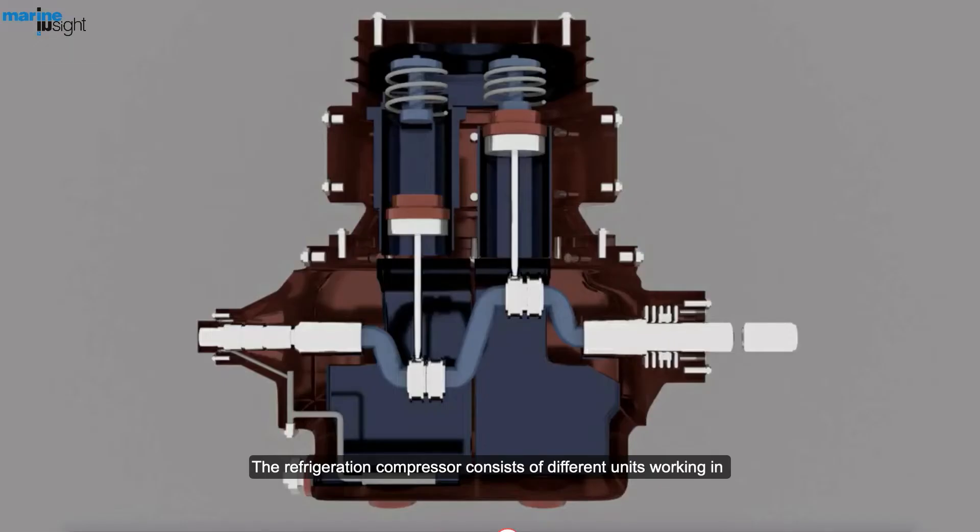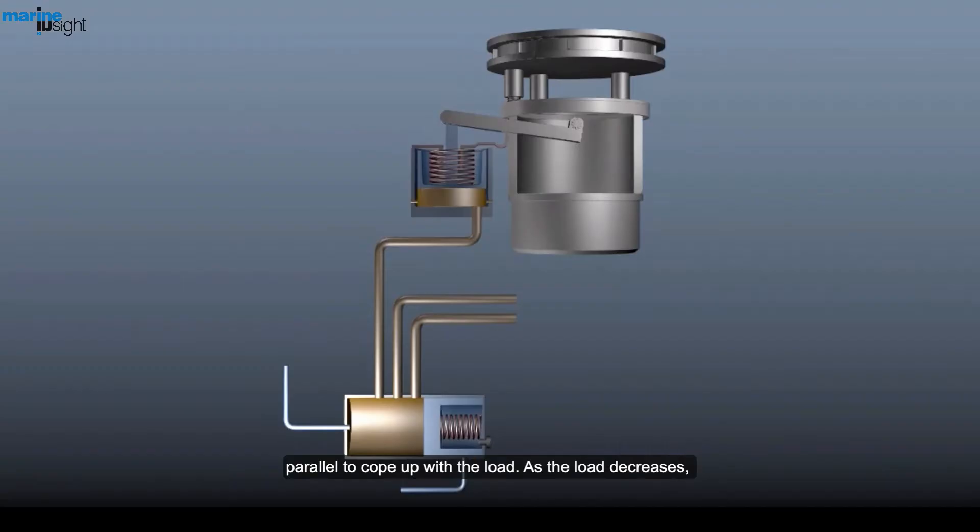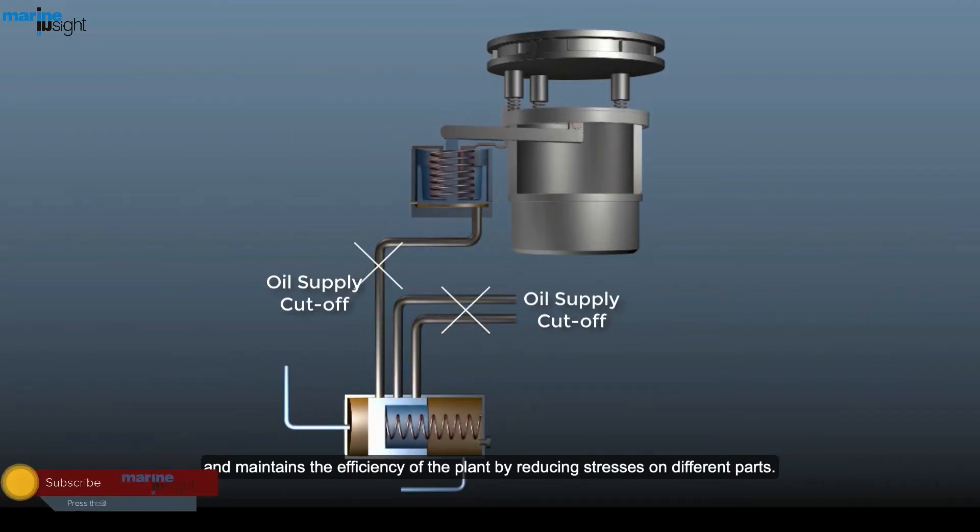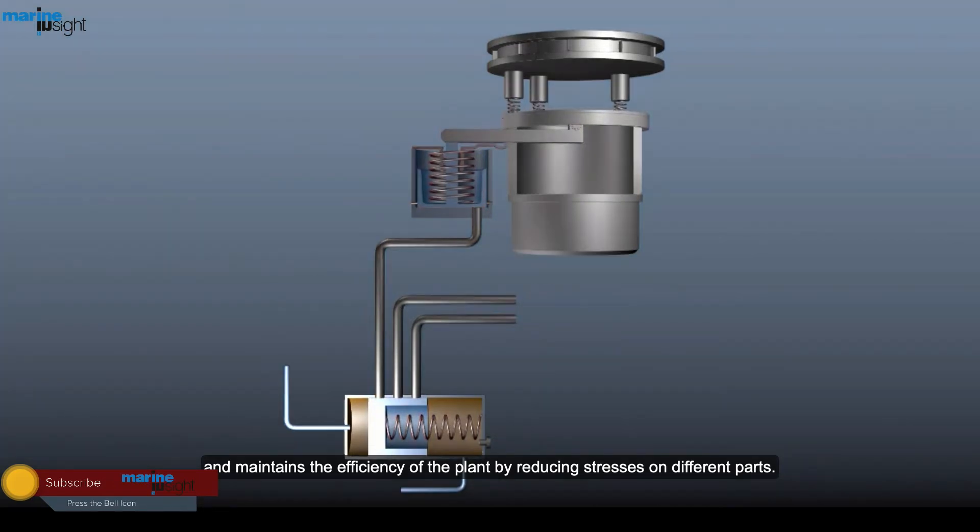The refrigeration compressor consists of different units working in parallel to cope up with the load. As the load decreases, the capacity control system cuts off one or more units, depending upon the load, and maintains the efficiency of the plant by reducing stress on different parts.